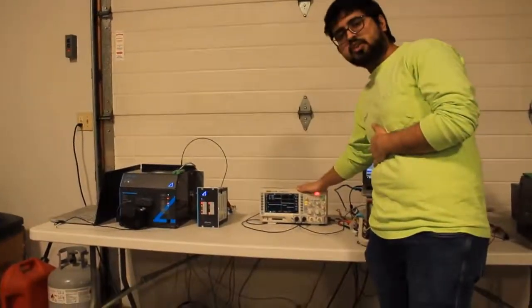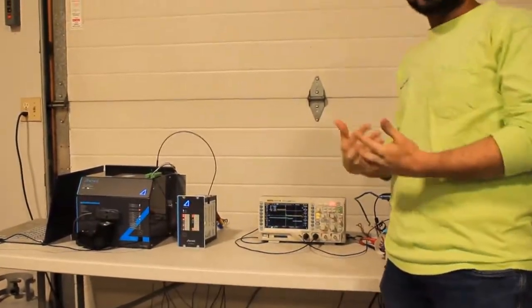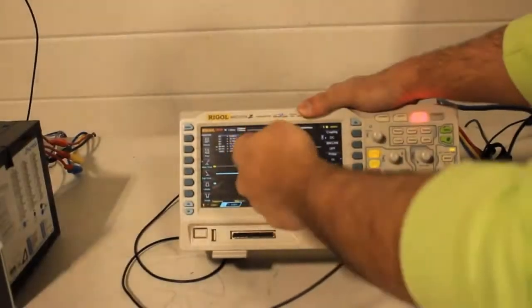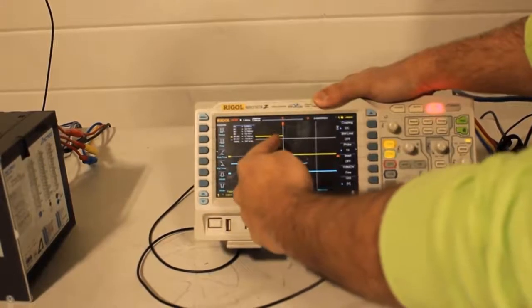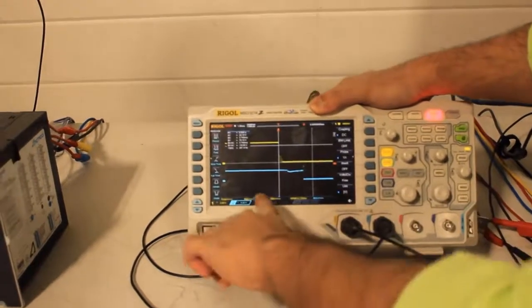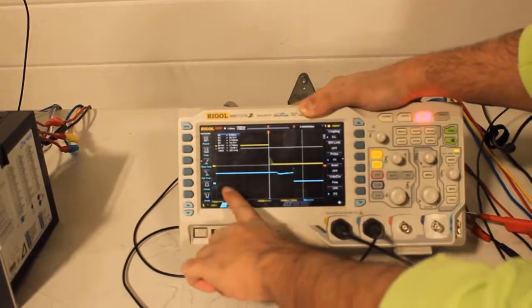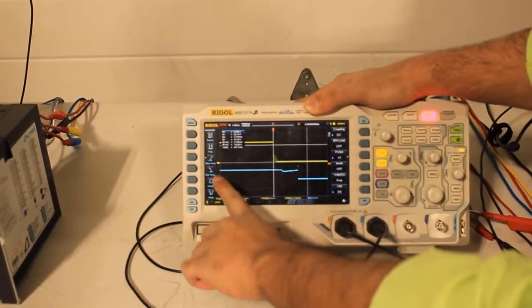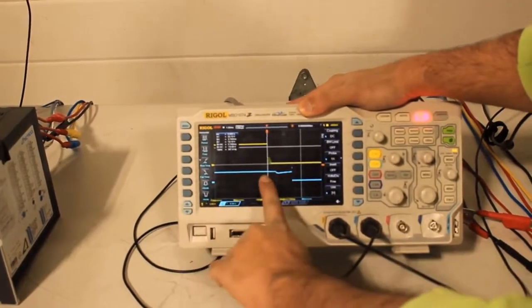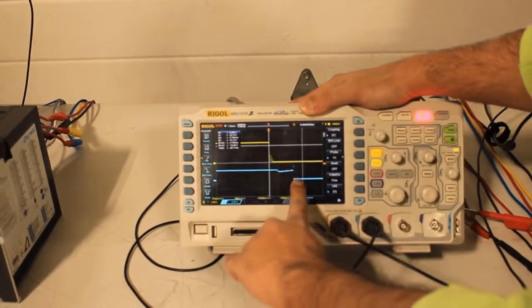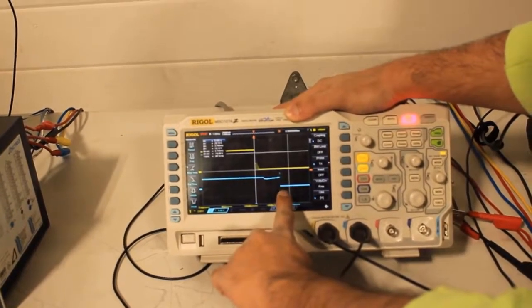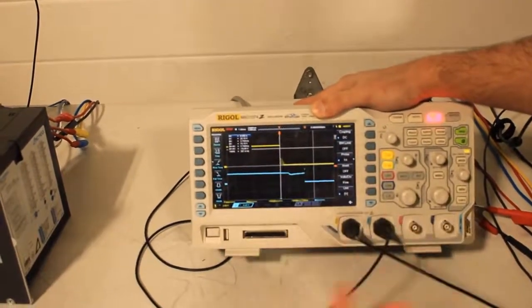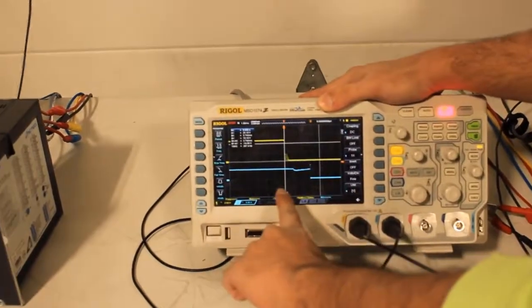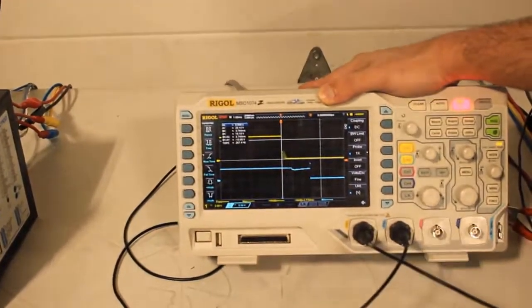We can measure the time here using this oscilloscope to make sure it was under 5 milliseconds. So as you see here, the yellow probe is for the flash, so it triggered at that particular second. And the blue line is the voltage. So there was 5 volts of voltage across one of the phases. So when the flash is triggered, it took almost 3 boxes for the voltage to drop to 0. And the scale is each box is 1 millisecond. So according to this, the quencher went off in less than 3 milliseconds.